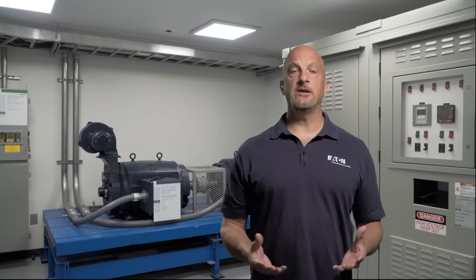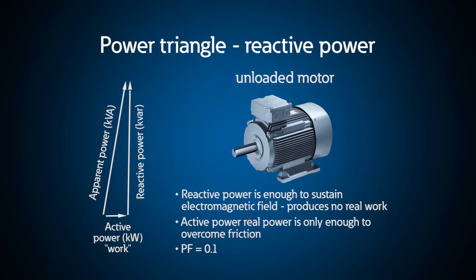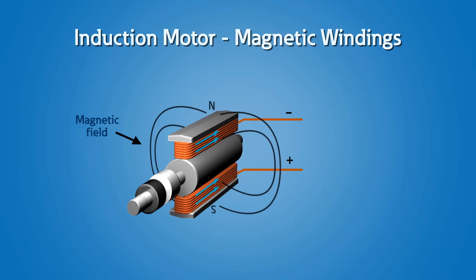For me, to understand what a VAR is, I personally like the following explanation using an induction motor. An induction motor needs a magnetic field to actually spin. So if you have an unloaded motor and apply voltage, the motor will spin but it's doing very little work — just enough to overcome friction. In order to make the motor spin, loaded or unloaded, you need a magnetic field. The power required to create this magnetic field is called reactive power, imaginary power, or VARs.